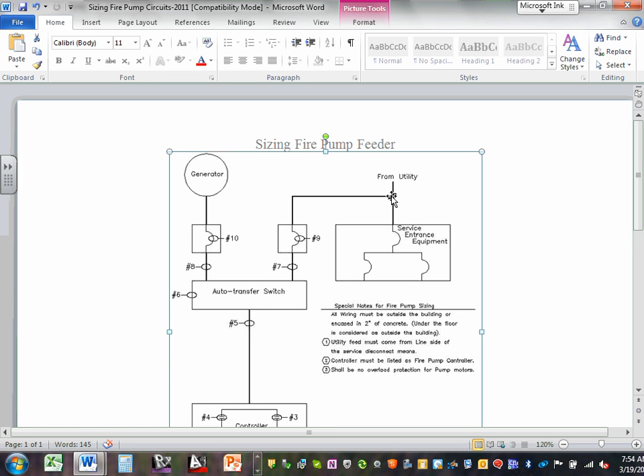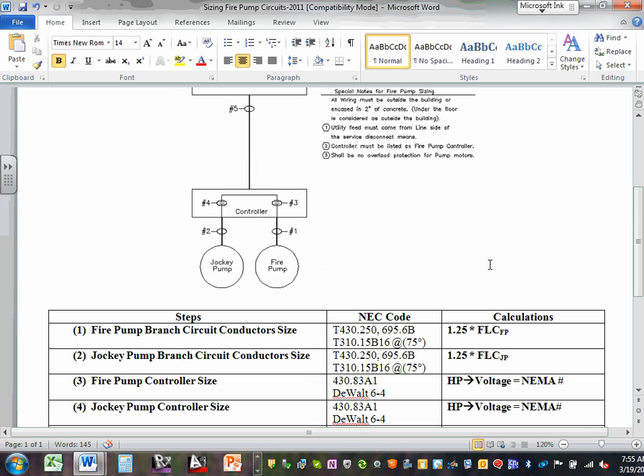Matt, I gave you 3 sheets. Grab the sheet that does not have a transformer in the middle here. What we're doing is sizing a system for a fire pump. Here is my jockey pump that pressurizes the system. The fire pump is the one that pushes pressurized water into the sprinkler system.